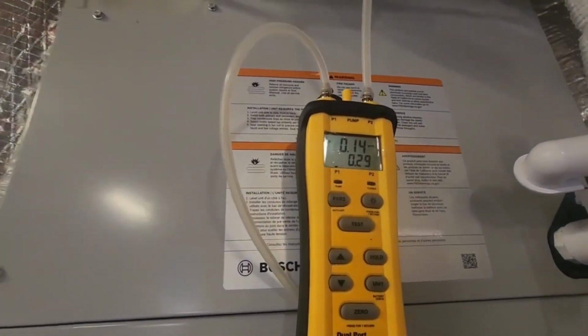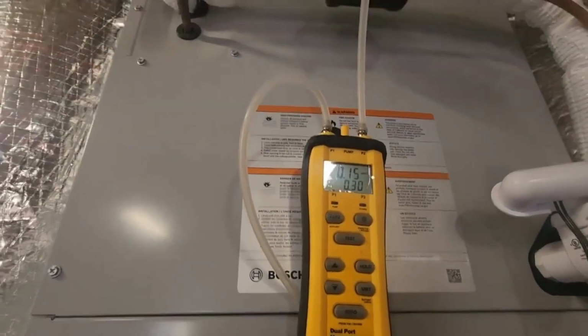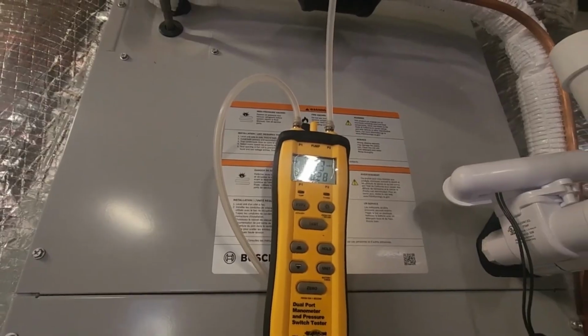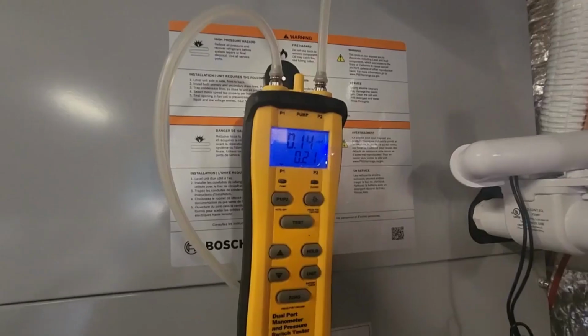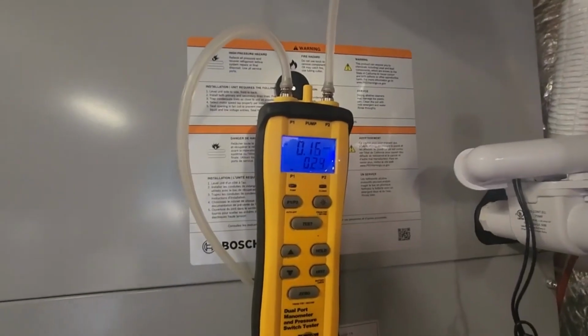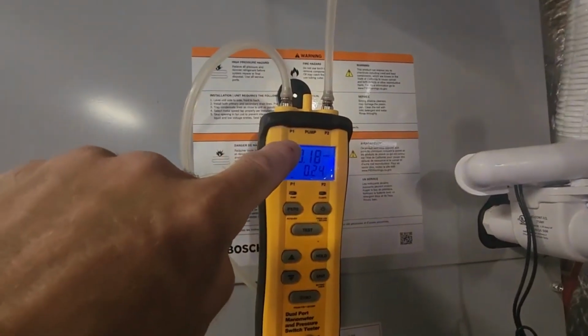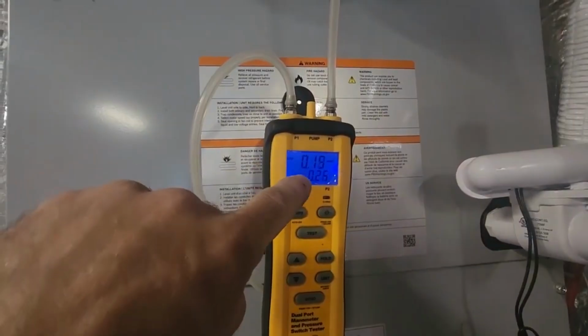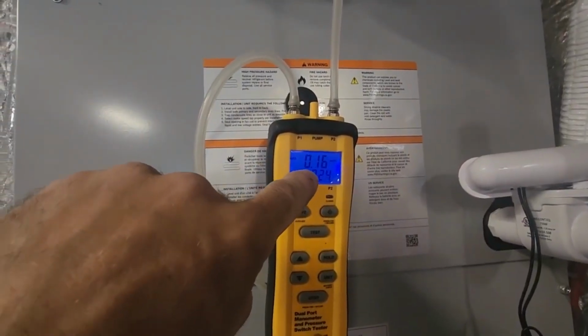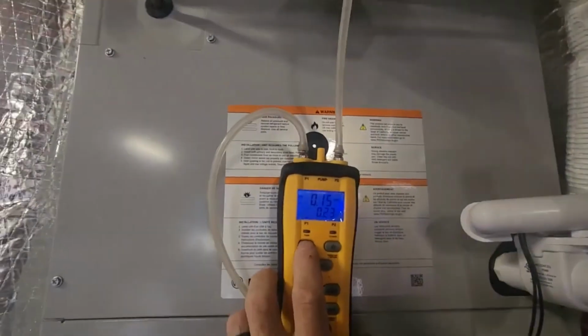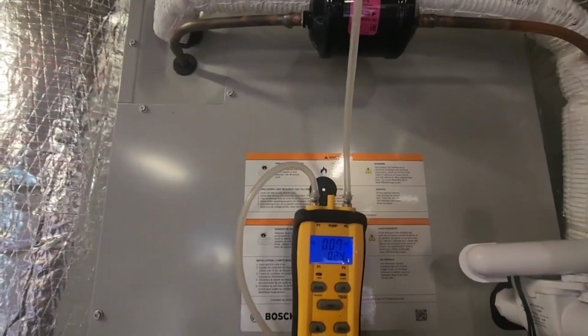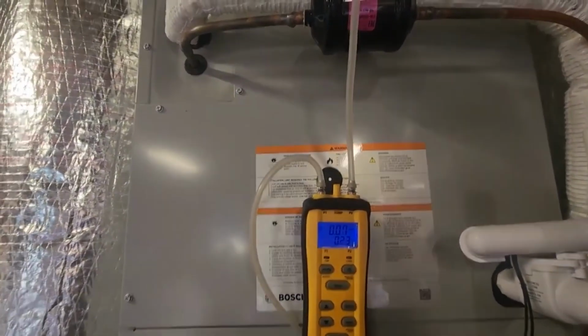So let's pull that filter out and see what we got, and we'll do the same thing. We'll do each zone, and then we'll do both wide open and see what we got. Check that out. 0.16 on our supply, 0.17, 0.18, only 0.08. Let's pump that over. 0.08, 0.07 on our return.